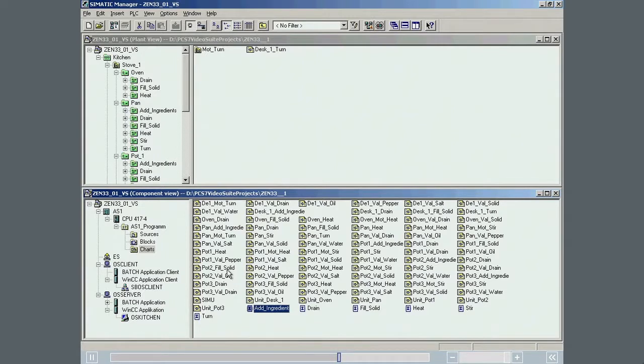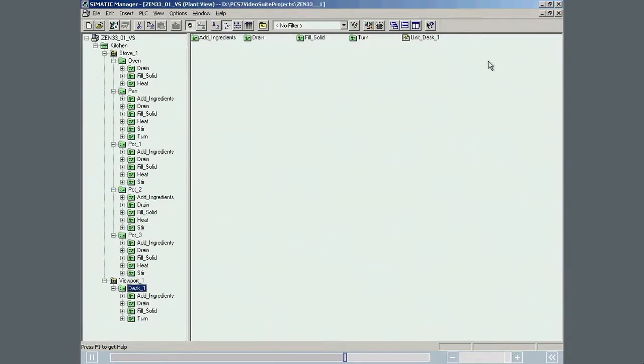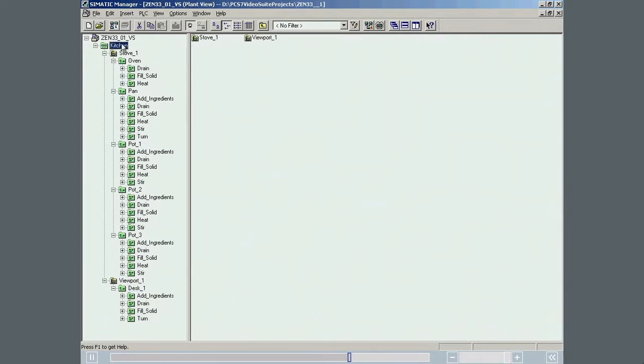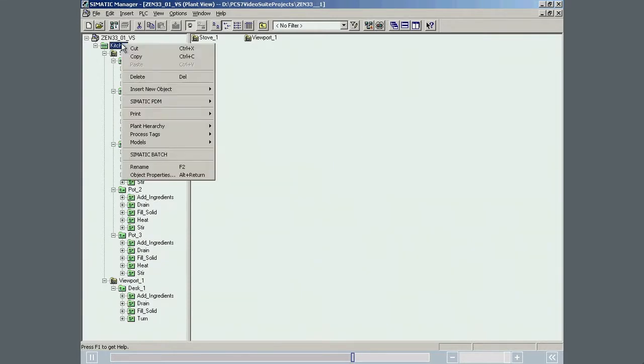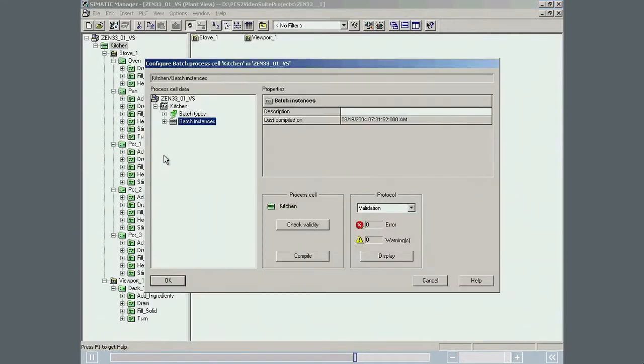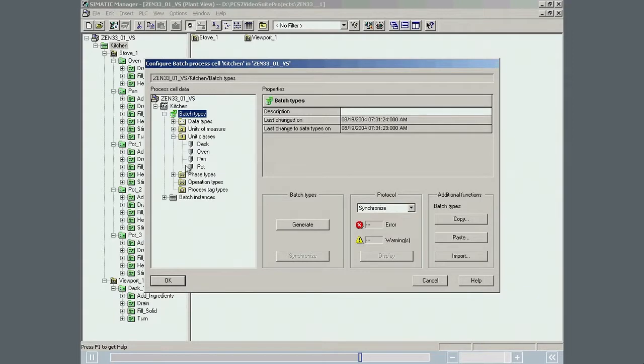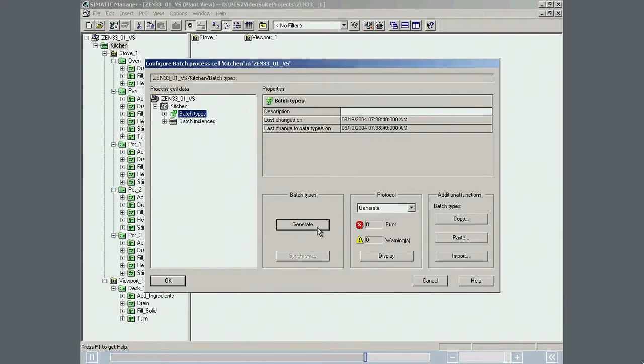In this section, we will generate the Batch types type descriptions, compile and download the Batch process cell data and compile the system alarm texts in the OS. The first step is to generate the process cell type descriptions. These will be the recipe building blocks. You have already seen this dialog during the definition of unit classes. Generation of the type descriptions is started and completed without errors or warnings.